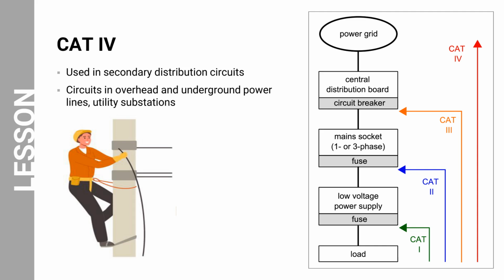The Cat rating of an EV charging station depends on the type of installation. For example, a Level 2 EV charging station installed in a garage would typically be rated Cat 3. This is because residential garages are typically considered low-voltage environments with minimal exposure to transient voltages. A Level 3 EV charging station installed at a commercial or industrial location would typically be rated Cat 4, because such locations are often exposed to higher voltage levels and transient voltages due to the presence of heavy machinery and industrial equipment. In summary, a EV charging station's Cat rating depends on the installation type to ensure that the equipment can withstand the expected voltage levels and transient voltages in the specific environment where it is installed.